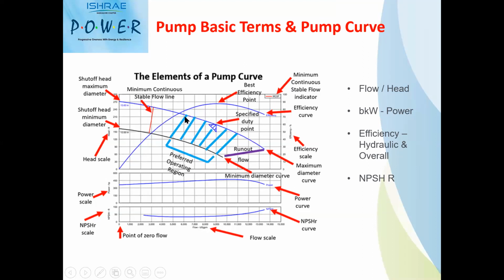So typically whenever we are selecting a pump, we always prefer to select a pump very close to the best efficiency point. There are ASHRAE guidelines which define the minimum range and maximum range beyond the BEP at which a pump has to be selected. The y-axis values are efficiency values, wherein you can see how the efficiency behaves. And then there is something called minimum continuous flow. For a particular size of selected pump with a fixed impeller diameter, what is the minimum flow it can take, beyond which it is not advisable to operate the pump?